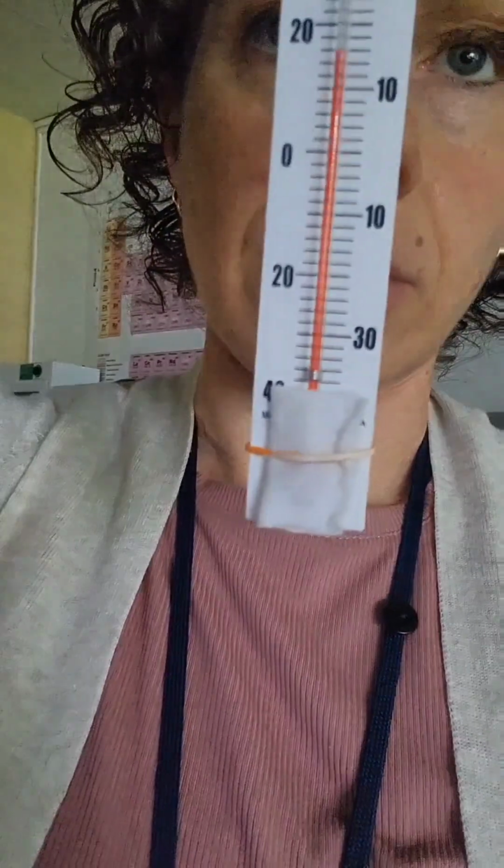For like a minute. You don't want the thermometer to read the temperature of the water you put on it. Like if you use hot water or ice water, it's going to throw things off. You want it to be just wet, just damp. Give it time for the thermometers to adjust. And then read your dry thermometer, read your wet thermometer, and check your reference table. You're going to do this inside and outside.